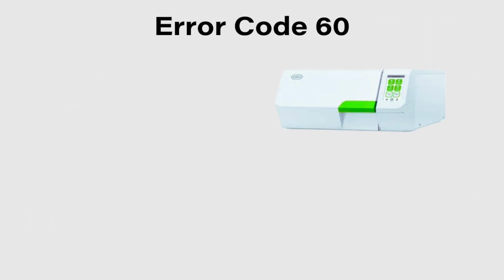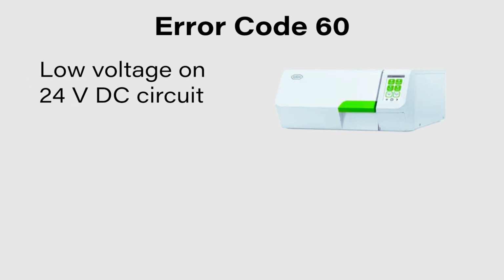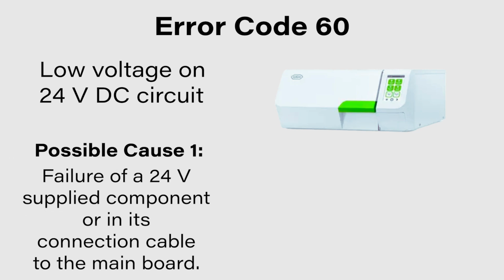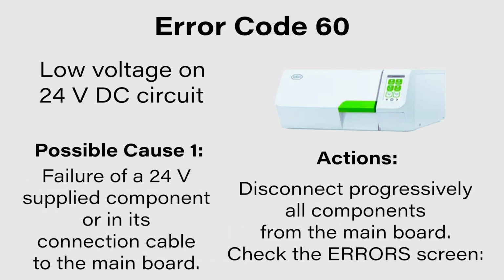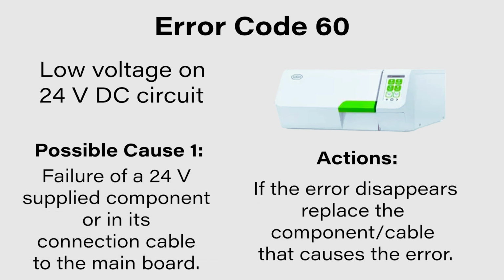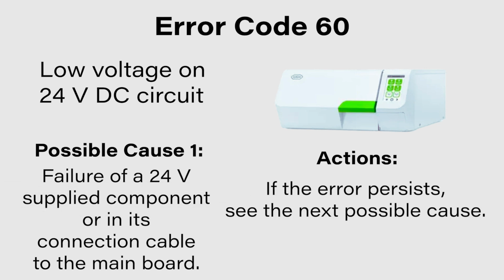If your W&H Lexa Mini sterilizer displays an error code 60, this means that there was low voltage on the 24-volt DC circuit. The first possible cause is a failure of the 24-volt supplied component or in its connection cable to the main board. For this, disconnect progressively all components from the main board. Check the error screen. If the error disappears, replace the component or cable that causes the error. If the error persists, see the next possible cause.